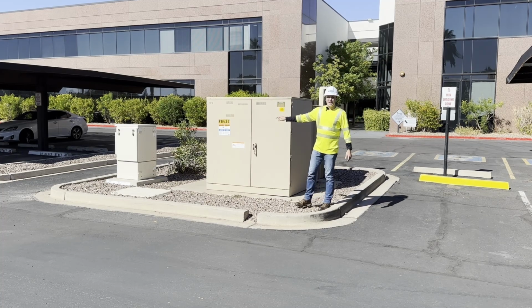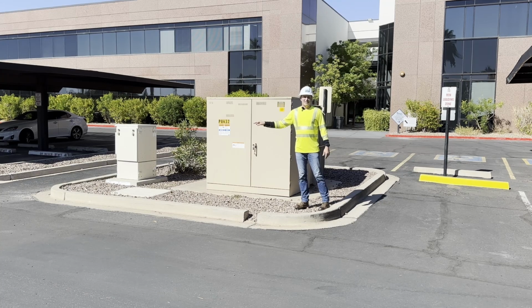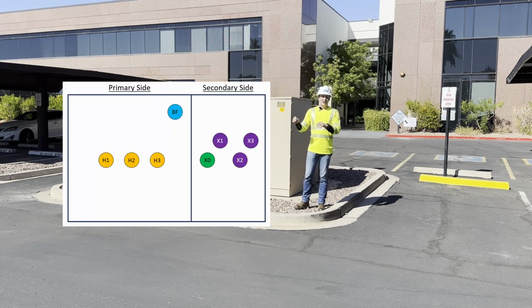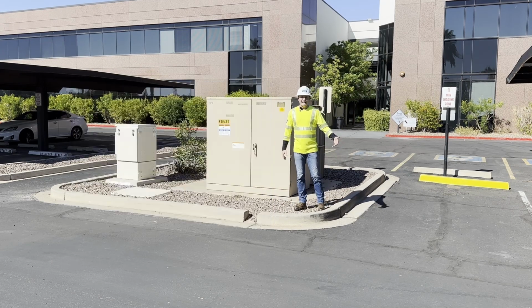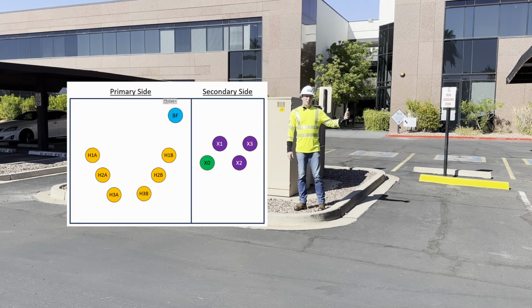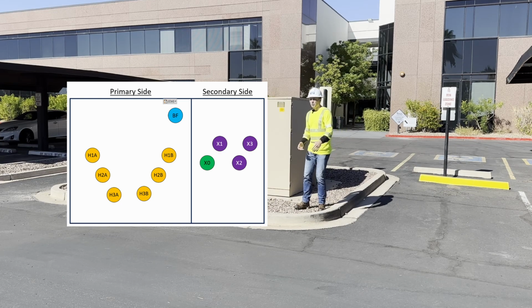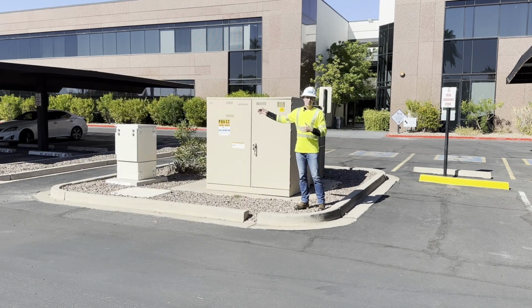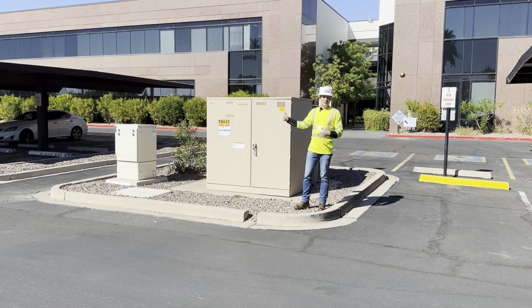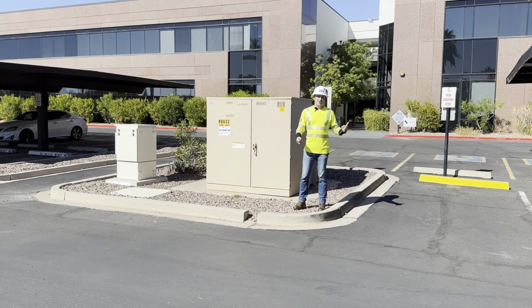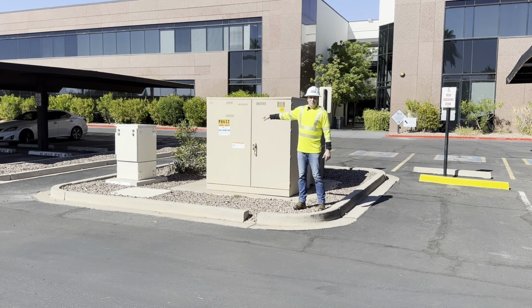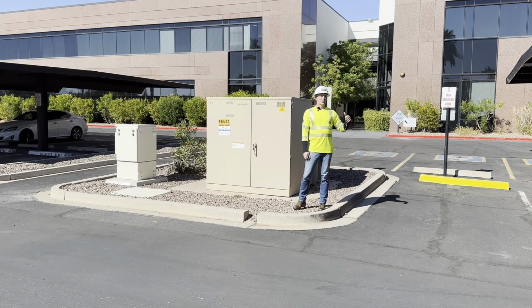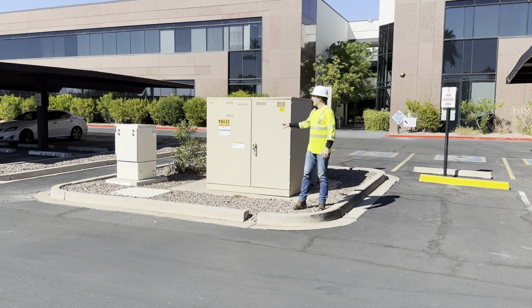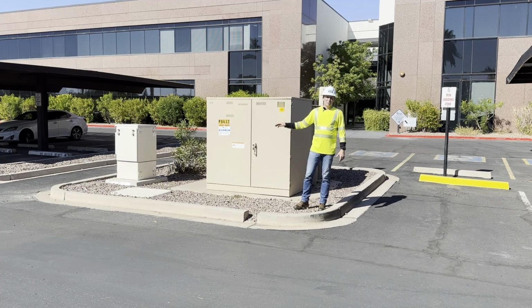So on the primary side, if there are just 3 bushings on that side - you can only see 3 lugs there - that is going to be a radial fed transformer. But if you see 6, then you know that's going to be a loop fed transformer, because the primary is coming in, going into the transformer, going into the primary and secondary coils through that iron core to the secondary side. But also on a loop fed, if there's those other bushings there, it can then go out to another transformer, another service. So depending on which one you have is really important to know for your project.